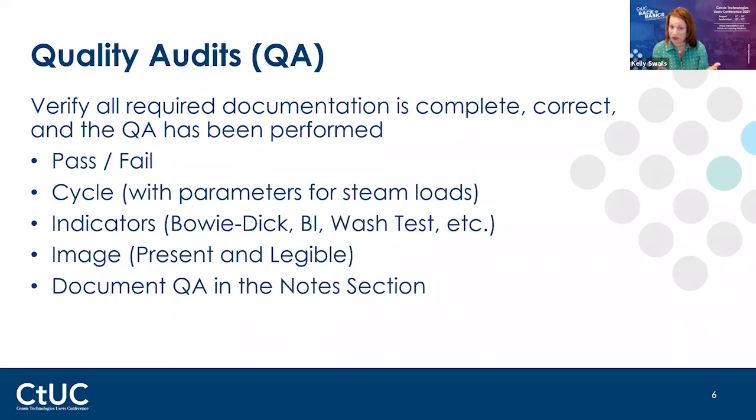Keep in mind, AAMI guidelines, so all this information we're putting in CensiTrac, AAMI guidelines always states name, date, and time. If you're on paper and you're documenting anything, many times I see the date's at the top of the page, and then you're just documenting down. Rarely do I see the time, and or I see initials. Or you're trying to read handwriting. So even if all your documentation was complete on paper, is it though if you don't have a name and you don't have a time?